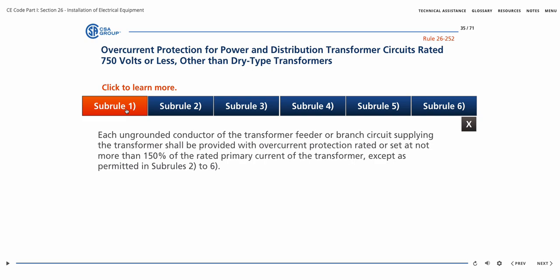In Subrule 1, each ungrounded conductor of the transformer feeder or branch circuit supplying the transformer shall be provided with overcurrent protection rated or set at not more than 150% of the rated primary current of the transformer, except as permitted in Subrules 2 to 6.